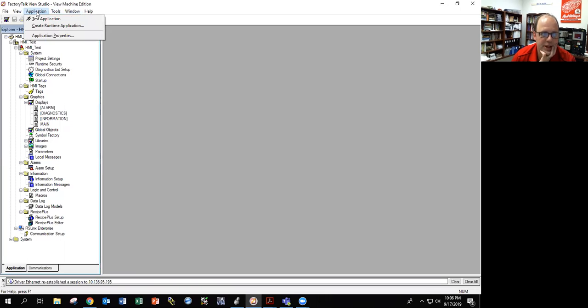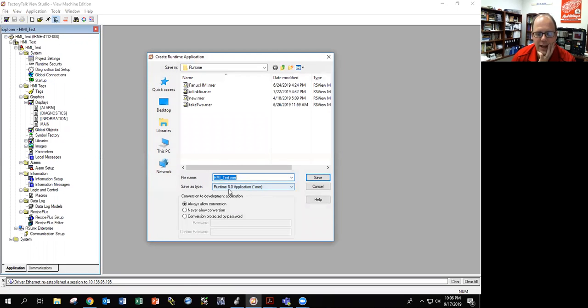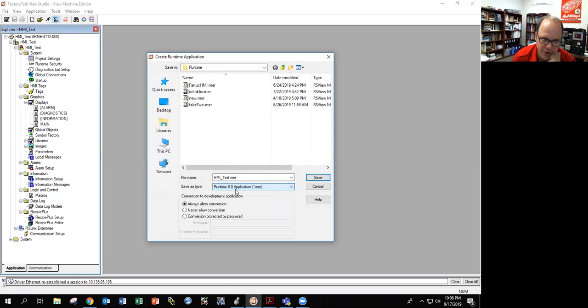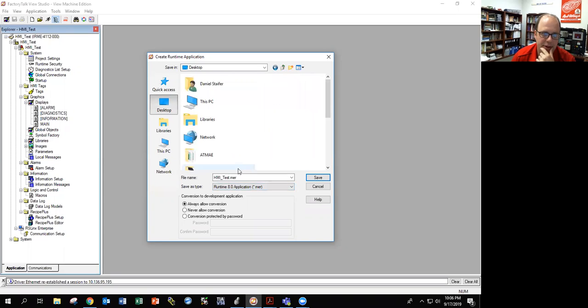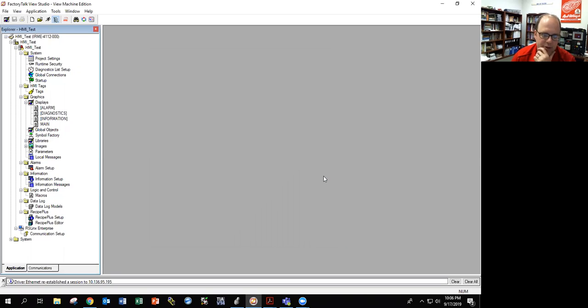The next step is to create the runtime application. It's important that your runtime application version matches whatever is on your HMI. I'm running Runtime 8 on this computer, so I can only put on Runtime 8. I'll save it to the desktop, call it 'HMI test MER,' and save. It's going to now build. If I did everything right, I can then transfer it to my HMI.